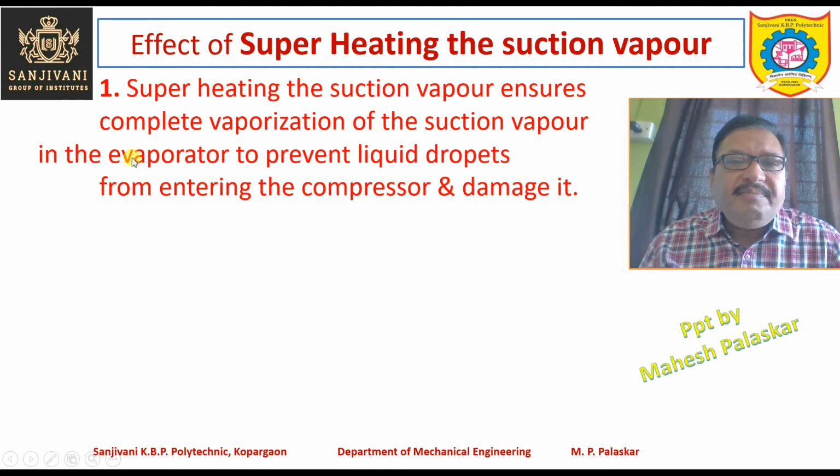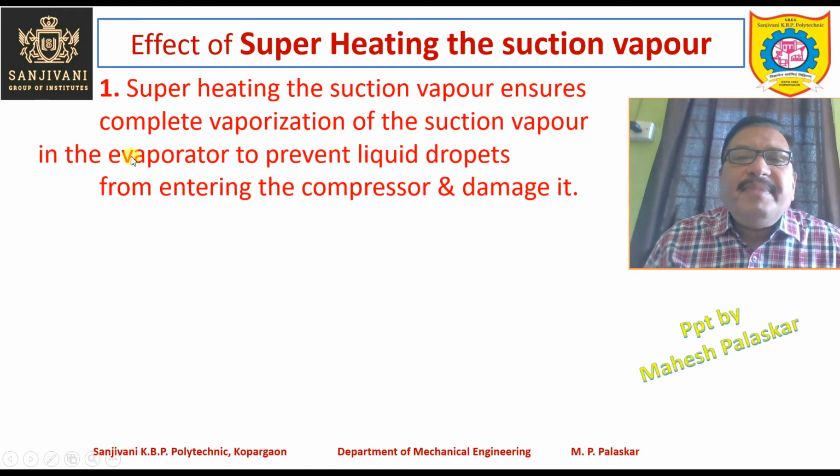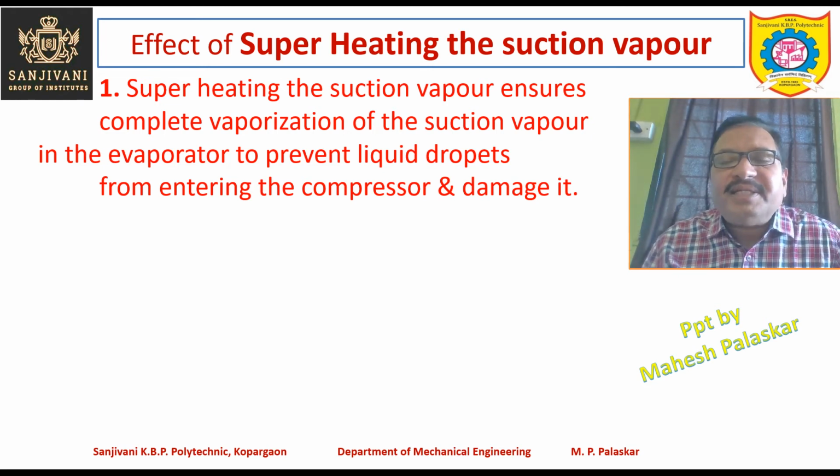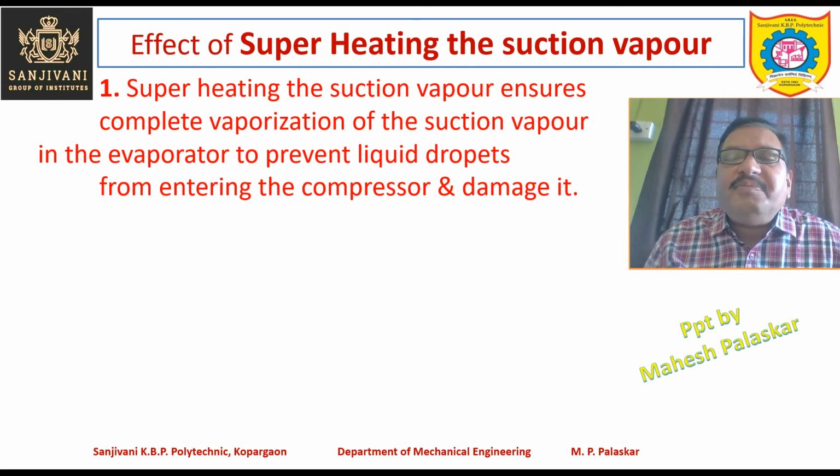the vapor, because these liquid droplets may damage the compressor. These liquid droplets of the refrigerant will carry the lubricating oil from the compressor outside the compressor, and thus there will be increased wear and tear and increased friction in the compressor, and that will decrease the life of the compressor.